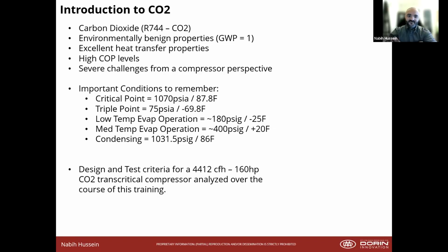Some important conditions, the critical point, which just means when you go into supercritical fluid, that's at 1070 psi and 87.8 F. So just 87.8 F, you can see that it's very easy to reach transcritical CO2. The triple point is at 75 psi and negative 69.8. That's where solid, liquid, and gas can exist. And the main issue there is dry ice.